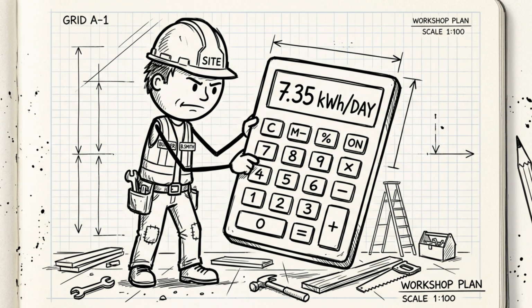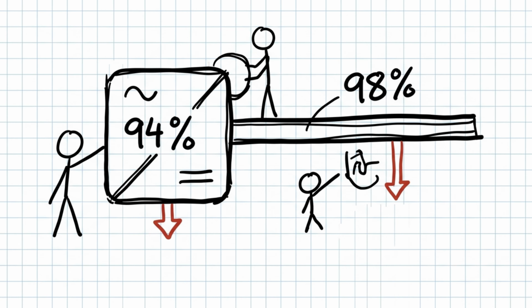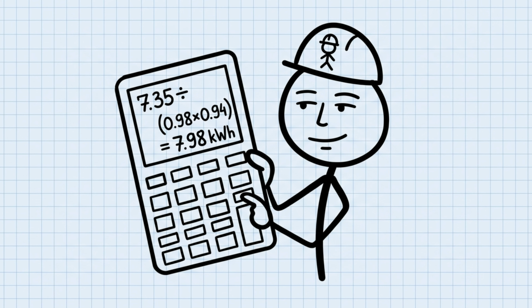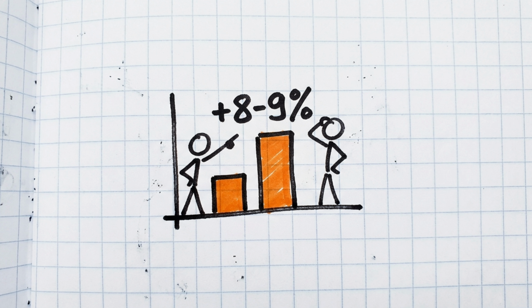Second, runtime. And this is where most people guess wrong. Say your chosen backup loads draw 7.35 kilowatt-hours over a day. You don't get to draw that straight from the battery. You lose energy at the inverter, roughly 94% efficient, and in the wiring, roughly 98% efficient. Divide instead of multiply. 7.35 kilowatt-hours divided by 0.98 times 0.94. Approximately 7.98 kilowatt-hours actually required from the battery bank. Those two small percentage losses compound. You need roughly 8 to 9% more battery capacity than your appliances actually consume.